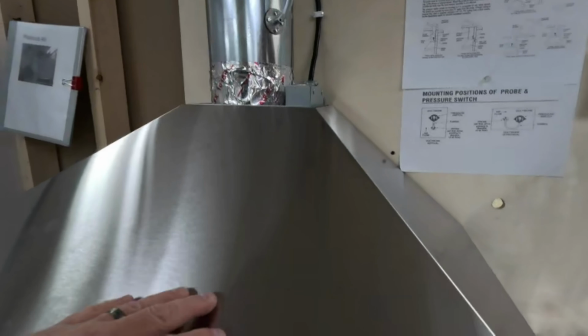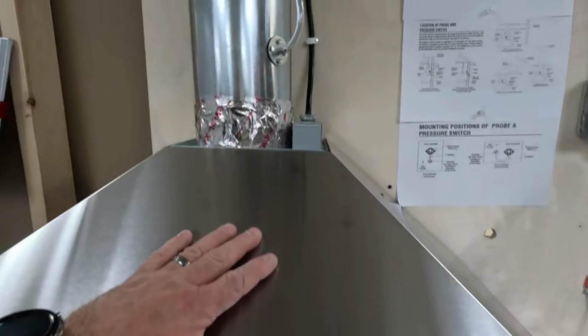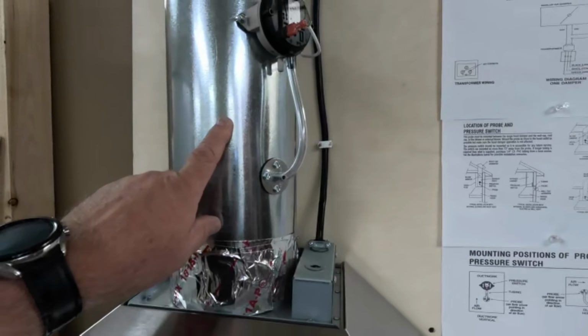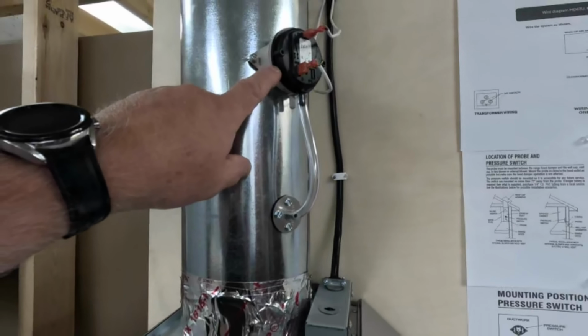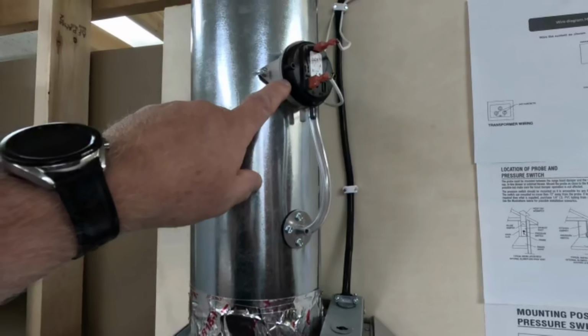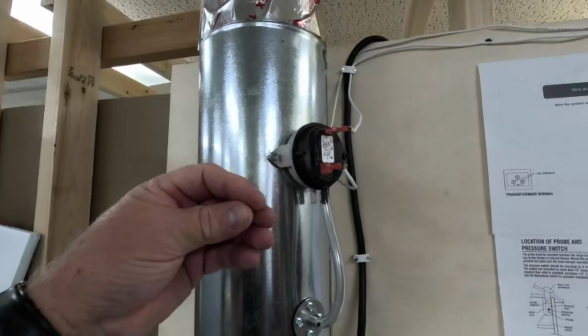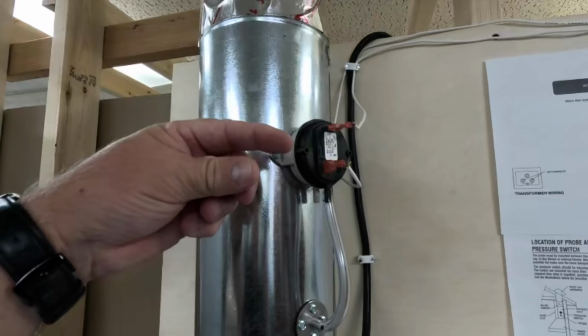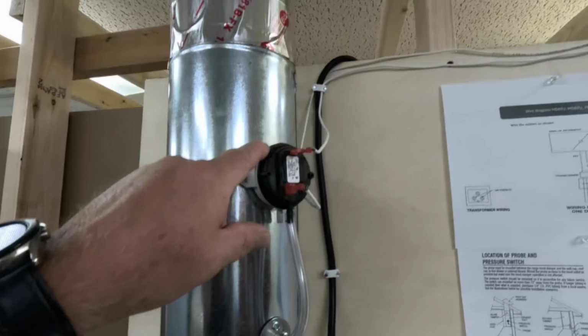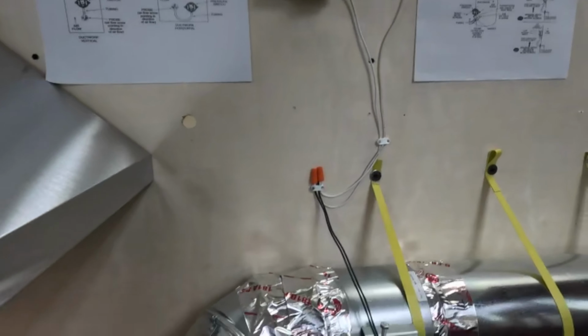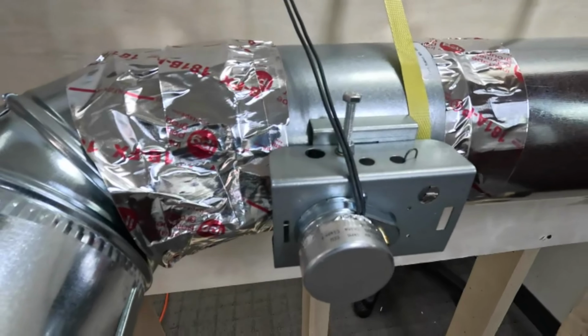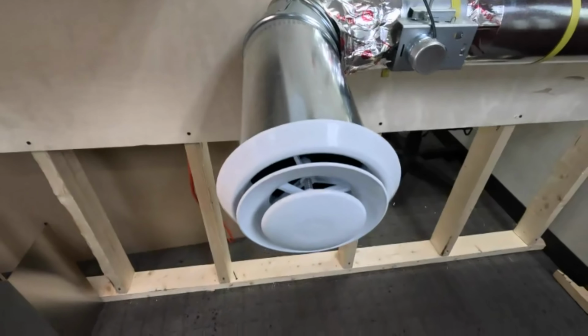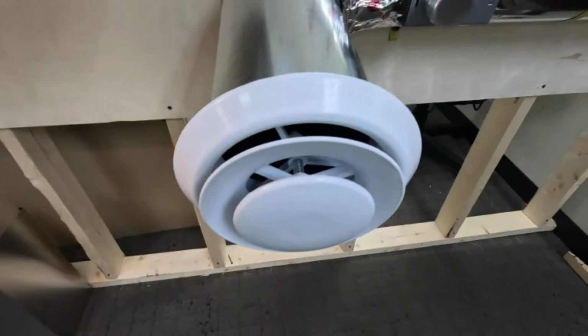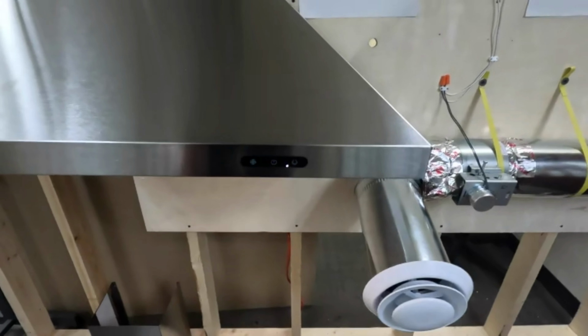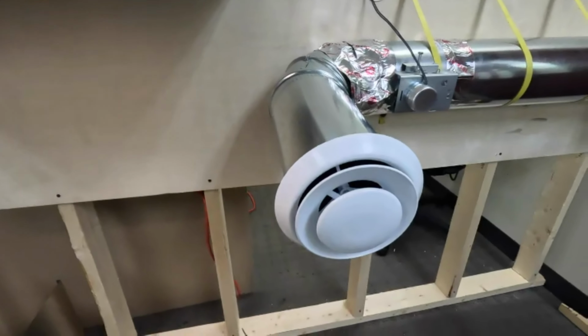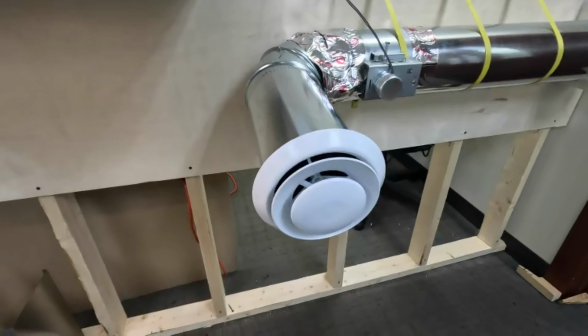So how it works, when I turn this range hood on, air flows up through this ductwork. The pressure switch senses it. There's always 24 volts to this pressure switch. This pressure switch has a bladder in it. When it senses air, the contact inside closes, sends the low voltage to the makeup air damper. The makeup air damper opens, and you'll start bringing in air through whatever venting system you had. Again, you're drawing through the range hood, and you're bringing it in through the makeup air ducting.